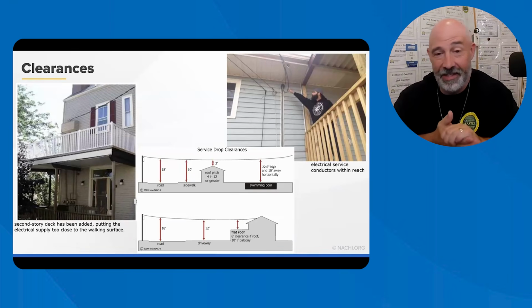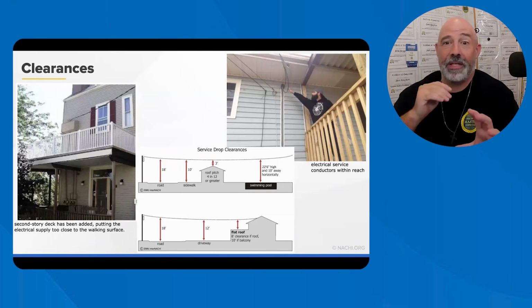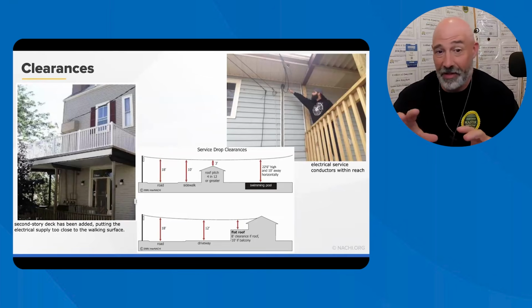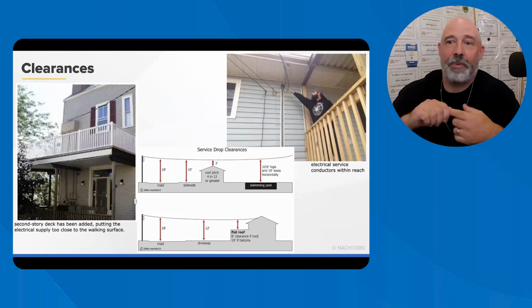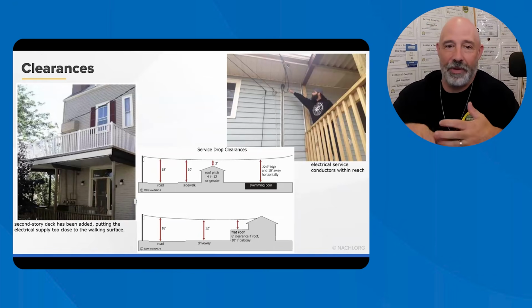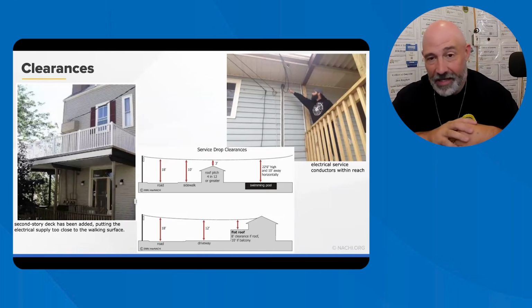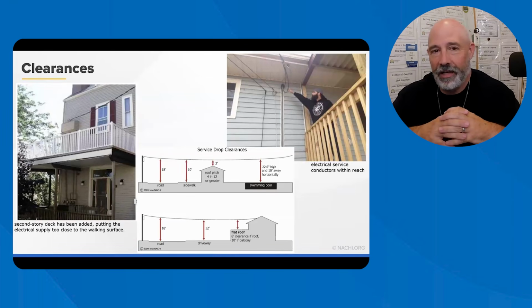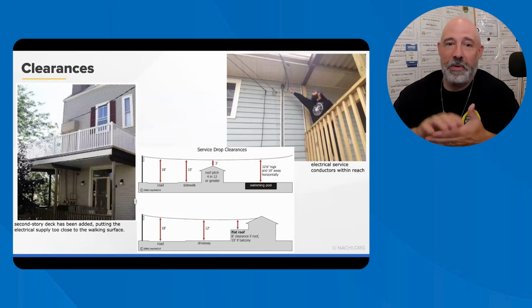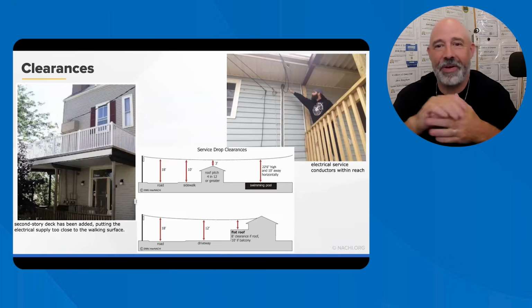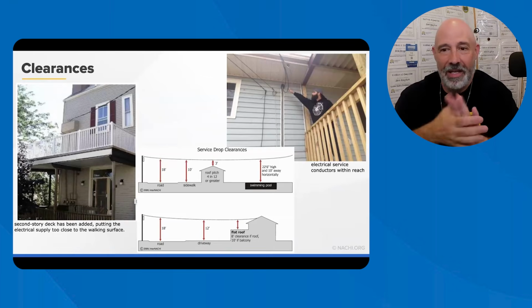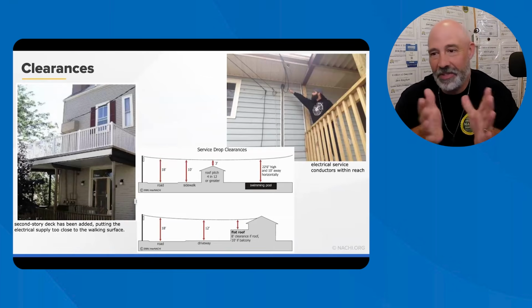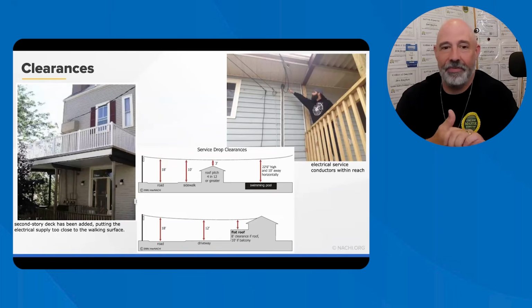If someone can reach and touch it from a balcony or window or whatever, it's worth a closer evaluation from an electrician. Inspectors should verify that overhead service conductors maintain proper clearance from roofs, decks, balconies, and so forth. As a matter of fact, I went to a 1910 house, and the service drop was 7 feet from the ground. Yes, I called that out, and the realtor never used me again. Home additions and renovations, such as decks and balconies, can sometimes place service conductors within reach. Make sure you're calling that stuff out.